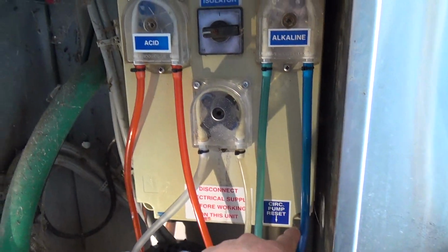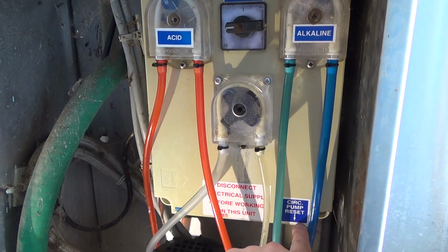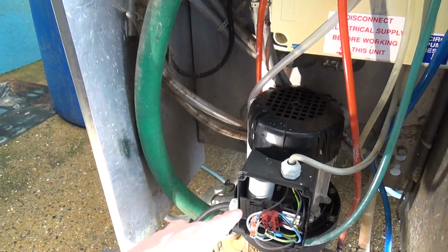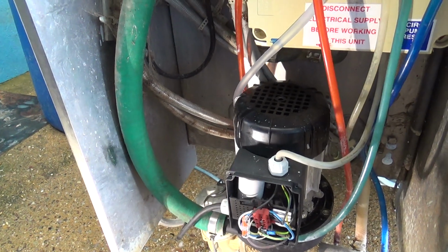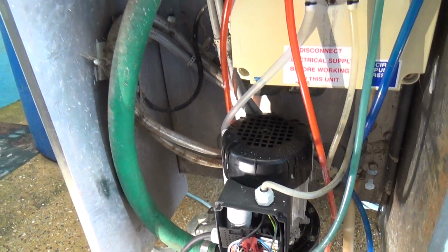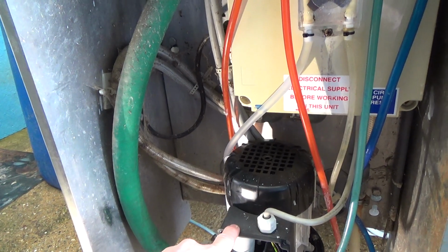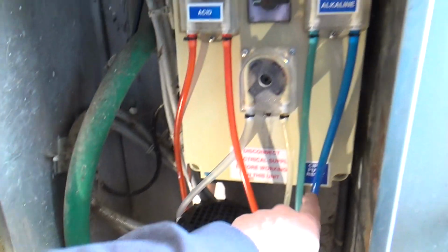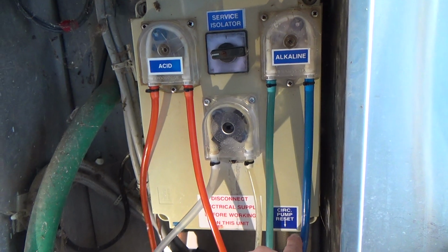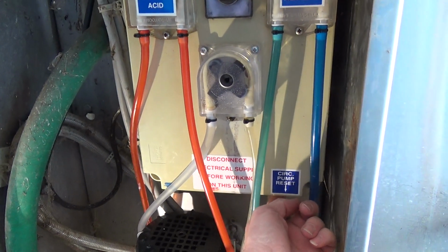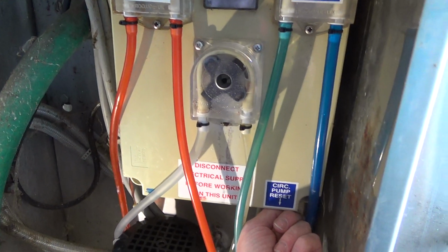Plus these little trips get tired over the years, so it's probably just knackered. But we will check the pump and make sure the capacitor's good, and we will put the thing on to rinse and check the run current isn't excessive. But I think we're just going to end up bypassing that thing for now. In fact, I don't even think they sell that as a spare part anymore. They don't put them on the new ones.